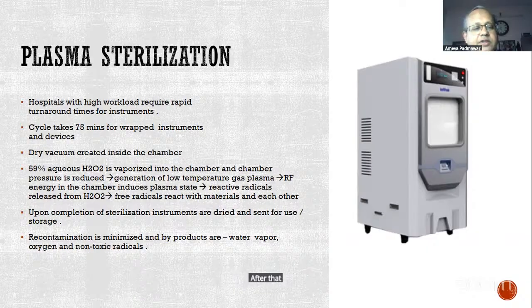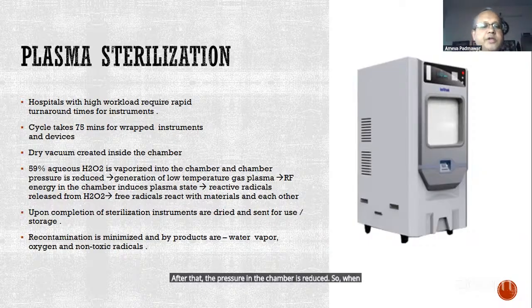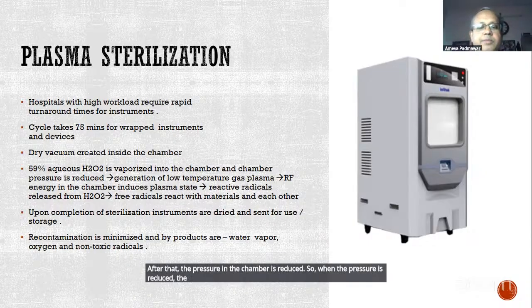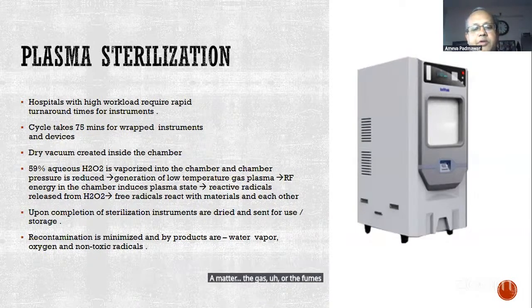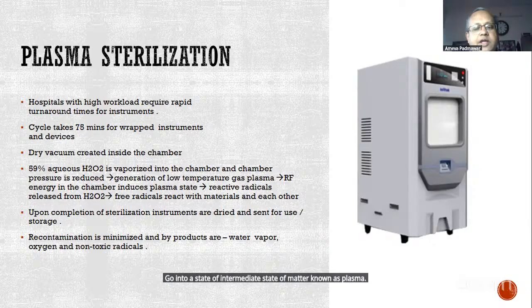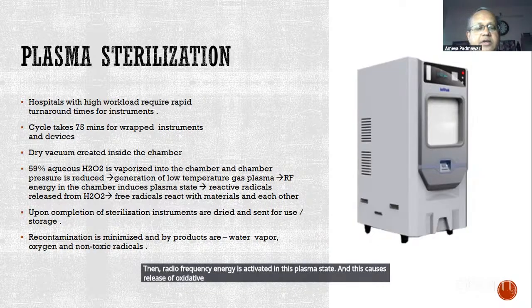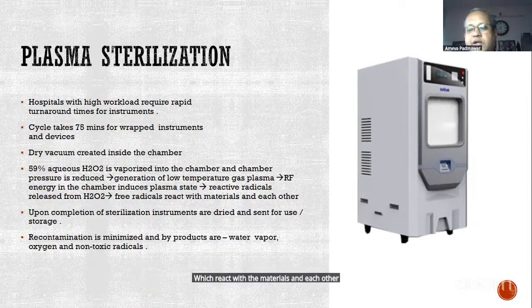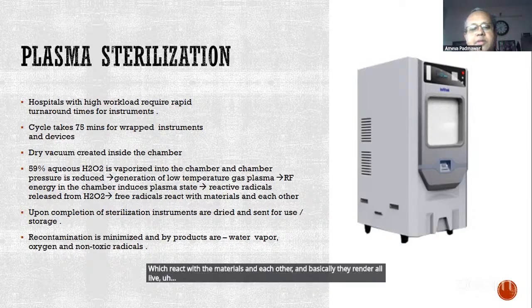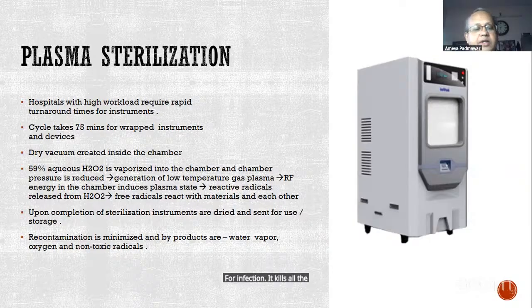After that, the pressure in the chamber is reduced. So when the pressure is reduced, at low temperature, the gas or the fumes of hydrogen peroxide go into an intermediate state of matter known as plasma. Then radio frequency energy is activated in this plasma state, and this causes release of oxidative reactive radicals from the hydrogen peroxide, which react with the materials and each other, and basically they render all live substances inactive for infection. It means it kills all the viruses and bacteria.